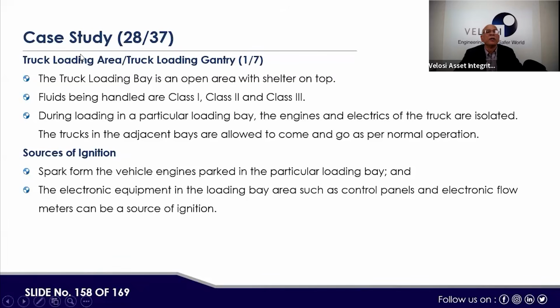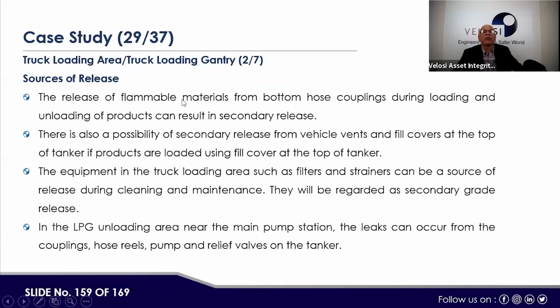Next, the truck loading area. The truck loading bay is an open area with a shelter on top. Fluids being handled are class 1, class 2, and class 3. This is the main area coming now. During loading in a particular loading bay, the engines and electrics of the truck are isolated. The trucks in the adjacent bays are allowed to come and go as per normal operation. Source of ignition: sparks from the vehicle engines parked in the particular loading bay, and the electrical equipment in the loading bay area, such as control panels and electronic flow meters, can be a source of ignition as well. Source of release: the release of flammable material from the bottom hose coupling during loading and unloading of the product can result in a secondary release.